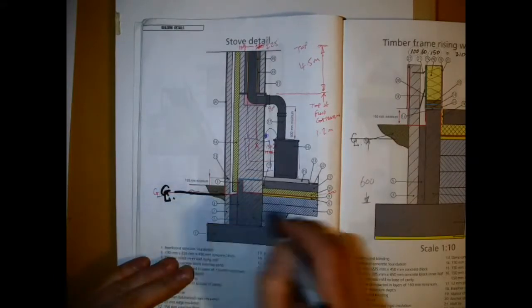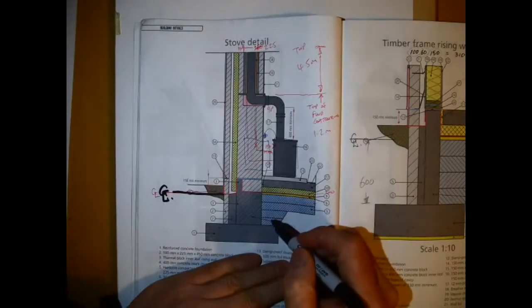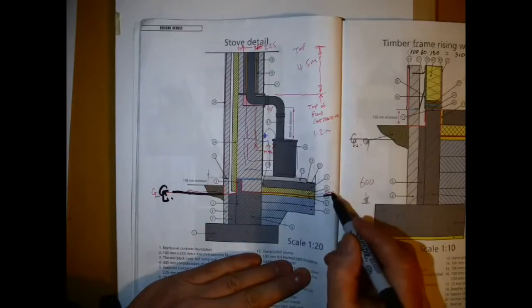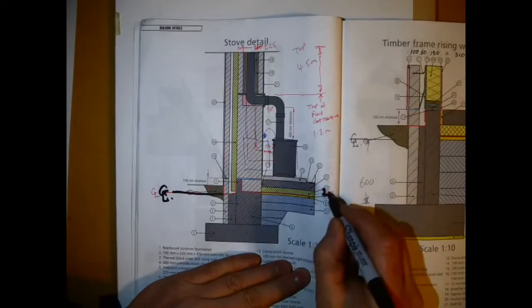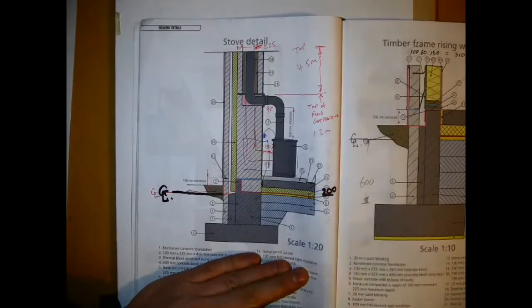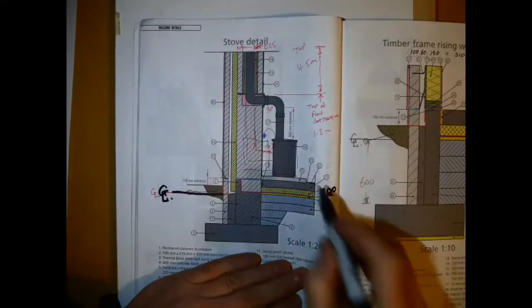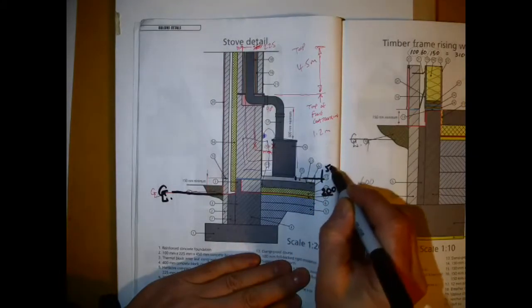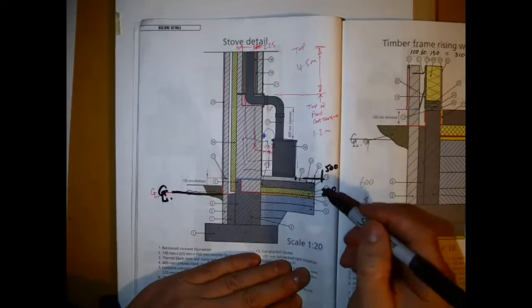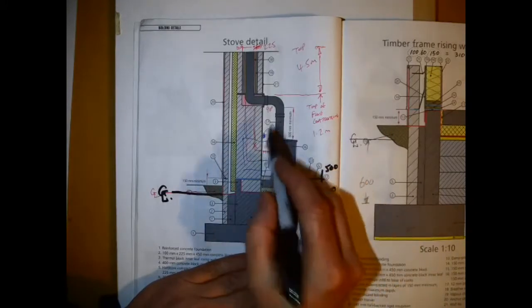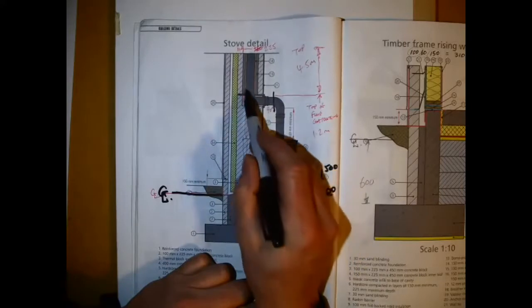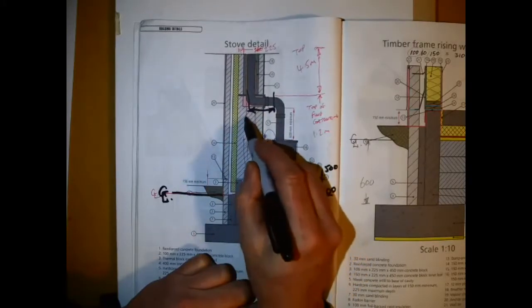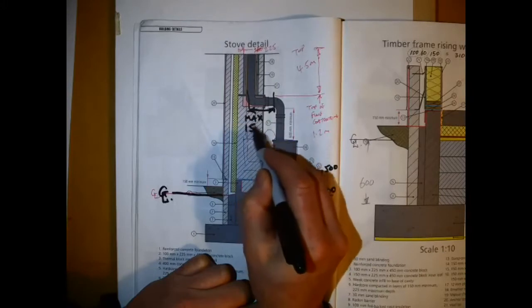In the workbook, you can see there's a few wee details here which I would change. We could get away with their insulation running under here, but it would have to be increased to 200. And one difficulty I have with this particular one, well, the hearth here should be extended out a little, but the flue, the arrangement with the flue, the space in here, there should not be a horizontal run of more than 150 millimeters where you have the flue, and that would be a no-no here.